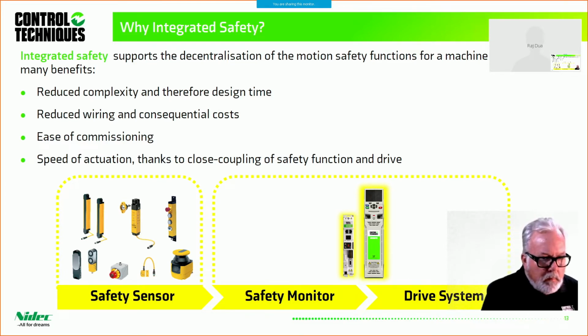We minimize the signal latency by having the safety sensors wired directly to the module, instead of having them come through a PLC and then using safe outputs from the PLC to come into the MiS module. Because everything is local, we can eliminate any PLC overhead or latency that could result. So that's an advantage of keeping the safety function at the drive level as it relates to the drive specifically.